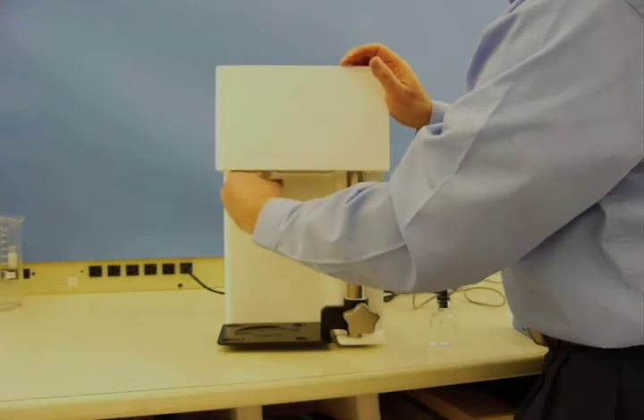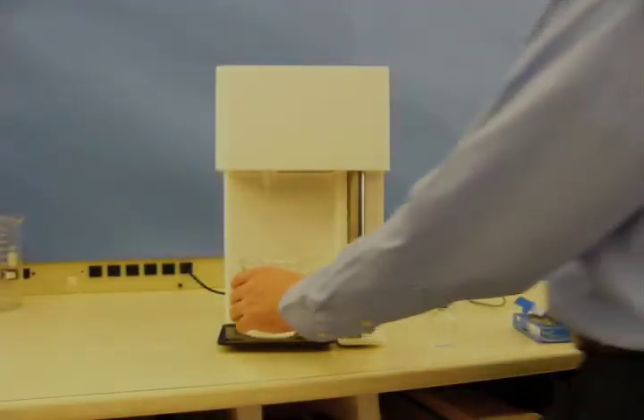Next, reconnect the inlet fitting and run a sample or two to ensure that the capillary is clean and no leaks were introduced during the process.